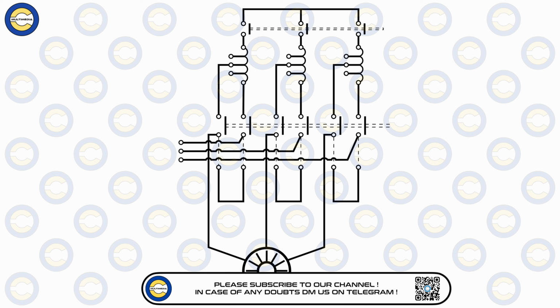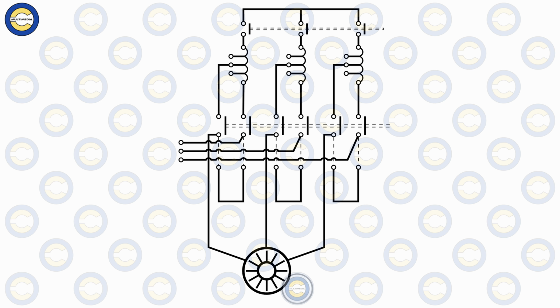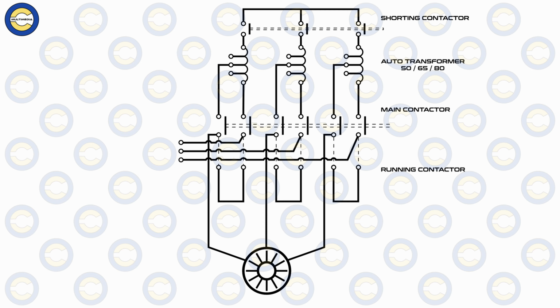Now that we are clear about the basic ideology of the auto transformer type starter, let us take out some time and run through the explanation of the circuit for this particular starter. In a typical setup of an auto transformer type starter, the main parts within the circuit would be the main contactor, the running contactor, the shorting contactor, also sometimes regarded as the starting contactor, and the auto transformer. The three-phase auto transformer included in the circuit would provide voltage tapping commonly at different ranges, for example 50%, 65%, 80%, etc. values of the line voltage.